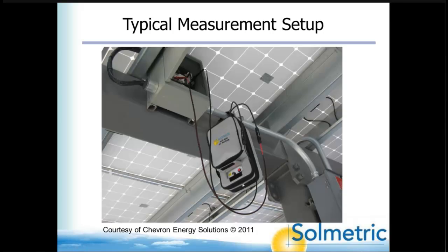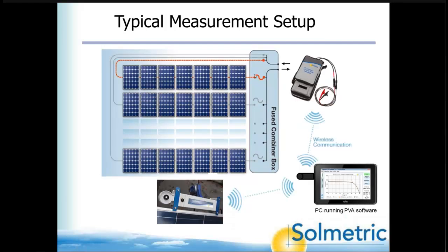Here's the typical setup. This happens to be a parking lot array, but could be any type of array. You put the PV analyzer near the combiner box. You open the DC disconnect. You lift all the fuses, and then you clip the giant alligator clips onto the bus bars, and then you insert 1 fuse at a time in order to make the measurement. Some of you have seen this drawing before. So this is that same thing, just converted to a cartoon. You're pushing in 1 fuse at a time to measure the corresponding string, using the combiner box as basically a single pole multi-throw switch. And you see the measurement on your display, and you press save, and you save it to a tree. And I'll show you that in a few minutes.